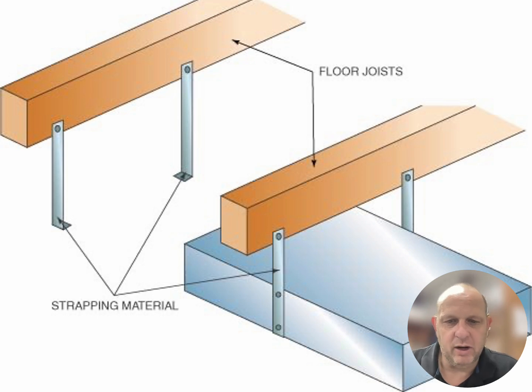Now, as we are spanning the metal duct and running that metal duct along the joists of the floor, or if we're going to be running it in the ceiling, we're also going to be running along the joists of the ceiling. If we're hanging this ductwork, we want to hang it every 3 to 4 feet. We want to put straps. Now, I usually use some of the drive cleats that we used back when we were connecting the two rectangular pieces together. I use those drive cleats as well to hang the ductwork on those floor joists as we're running them along the basement and/or the crawl space of that place.